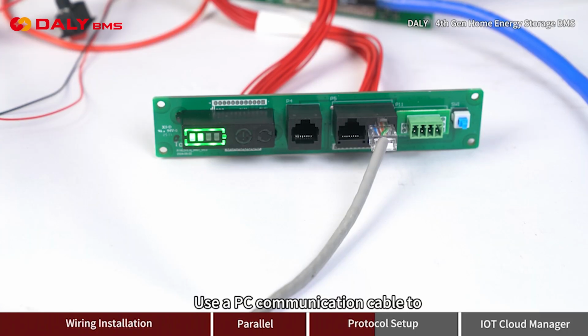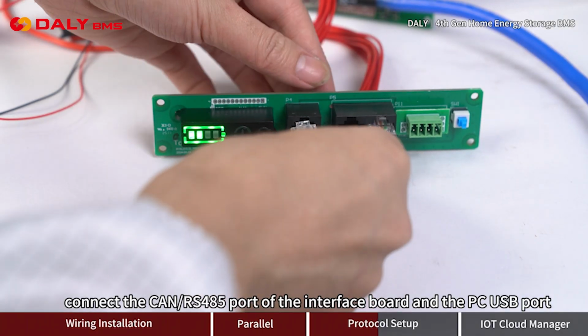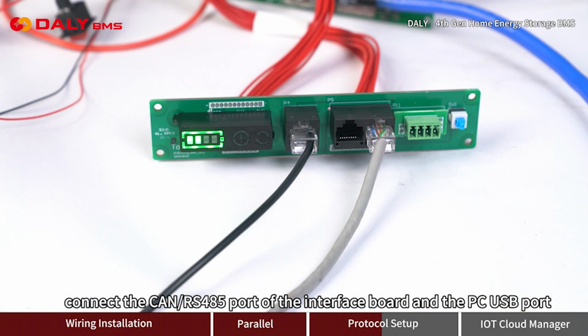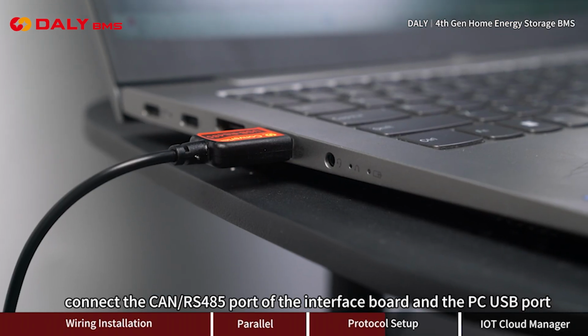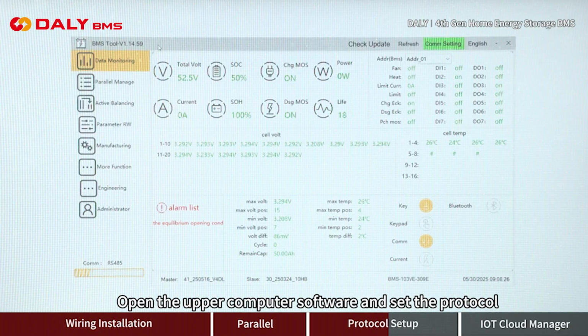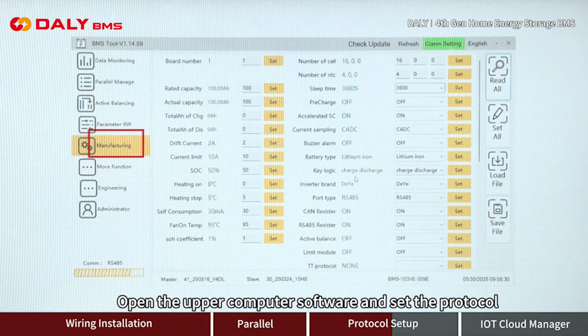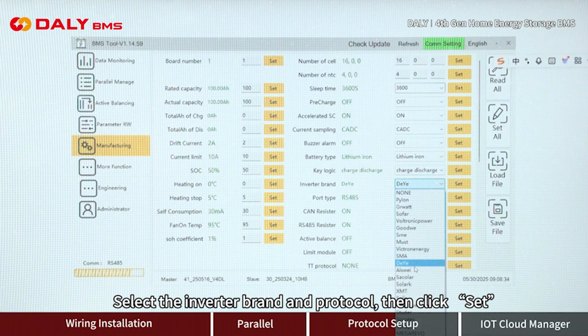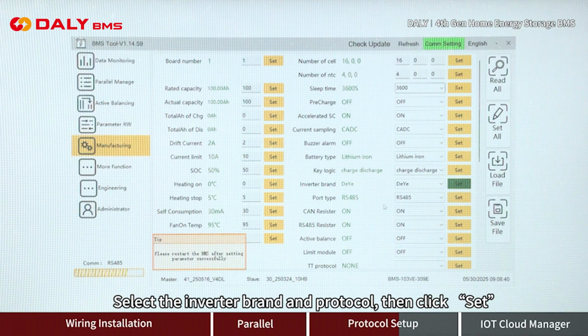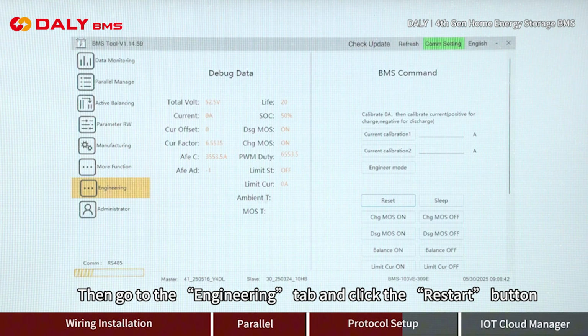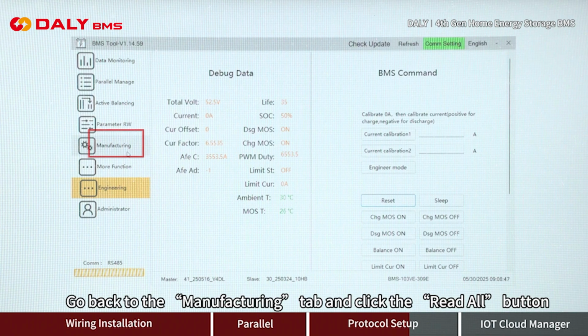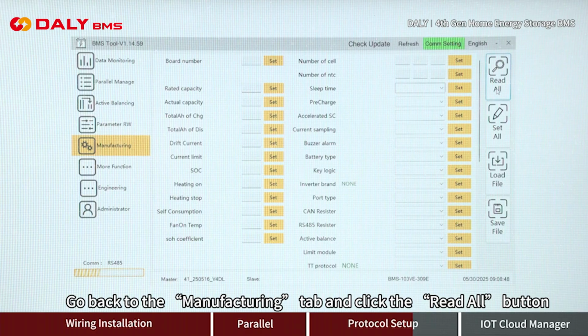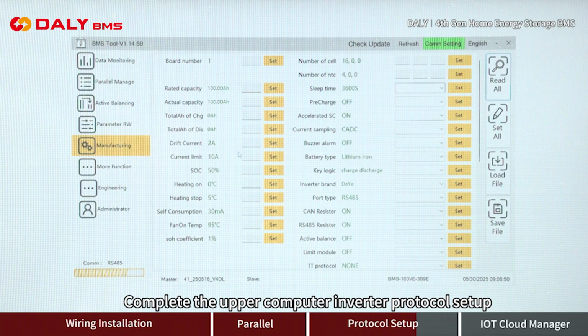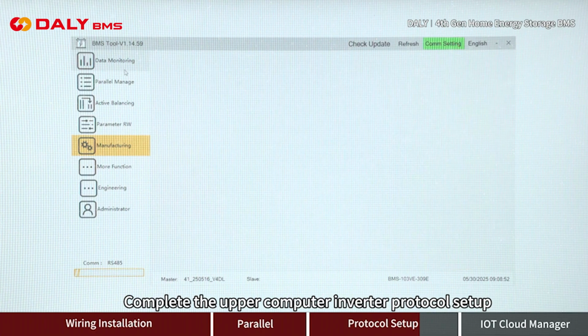Use a PC communication cable to connect the CAN/RS-485 port of the interface board and the PC USB port. Open the upper computer software and set the protocol. Select the inverter brand and protocol, then click Set. Then go to the Engineering tab and click the Restart button. Go back to the Manufacturing tab and click the Read All button. Complete the upper computer inverter protocol setup.